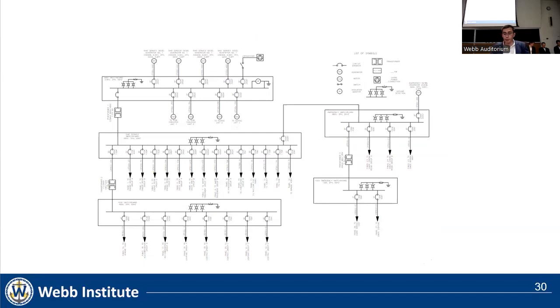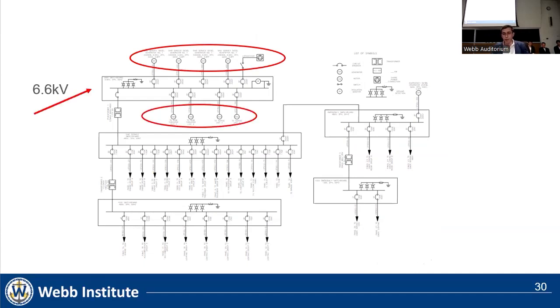Here's a one-line diagram for the NSV displaying a more detailed breakdown of the electrical system. At the top, we have 4 gensets. These provide power at 6.6 kilovolts, the thrusters' rated voltage, as shown by the fact that they are connected to the same bus bar. The power is transformed to 480 volts to supply the larger machinery loads, and the emergency generator is also rated for supplying this voltage as well.